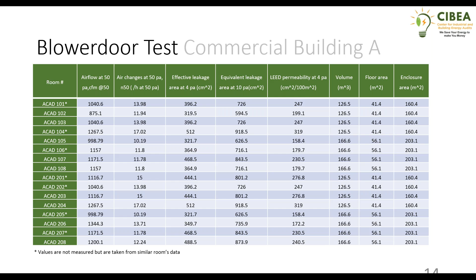I'm not going into detail on all of the columns, but this was the important point that I wanted to highlight here. After performing the blower door test, the ACH 50 value that we got for that building was 13.2, or actually it is the average for all 16 rooms in that particular building. We used a climate factor to convert it into a natural form. The climate factor for this particular building was 9.71, and that converted the ACH to 1.36 once the blower door is not installed.